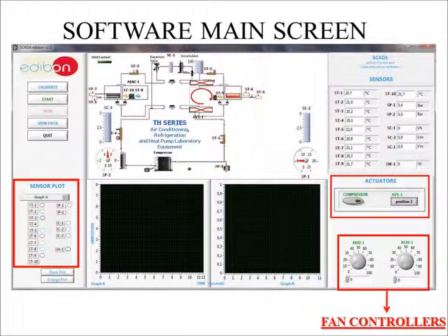The actuators are located in the middle right of the screen. Here is where you start the compressor and choose between position 1 and 2. It is very important to know that once you start the compressor, you can't change from position 1 to 2 or vice versa. Fan controllers are located at the bottom right. Here's where you control fan speed up to 100%.